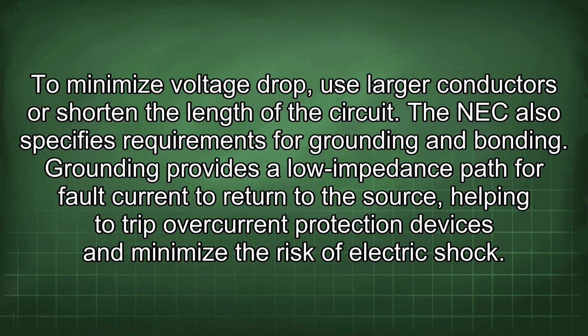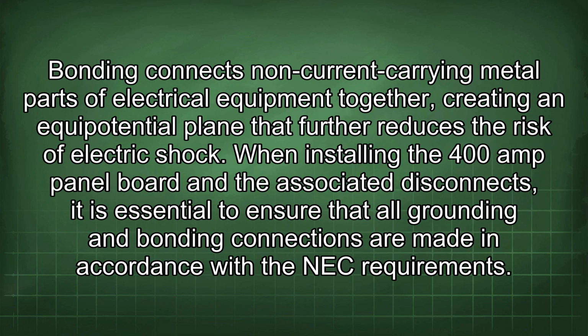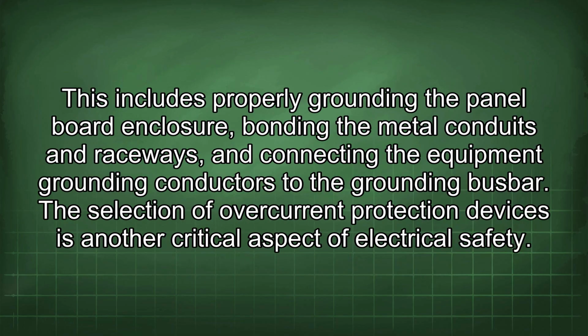The NEC also specifies requirements for grounding and bonding. Grounding provides a low impedance path for fault current to return to the source, helping to trip overcurrent protection devices and minimize the risk of electric shock. Bonding connects non-current carrying metal parts of electrical equipment together, creating an equipotential plane that further reduces the risk of electric shock. When installing the 400 amp panel board and the associated disconnects, it is essential to ensure that all grounding and bonding connections are made in accordance with the NEC requirements. This includes properly grounding the panel board enclosure, bonding the metal conduits and raceways, and connecting the equipment grounding conductors to the grounding busbar.